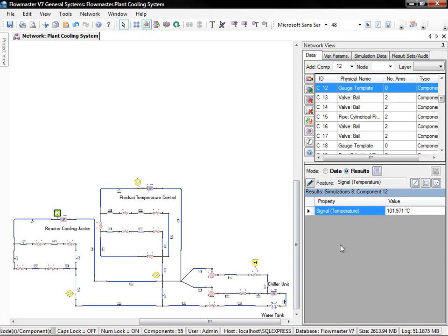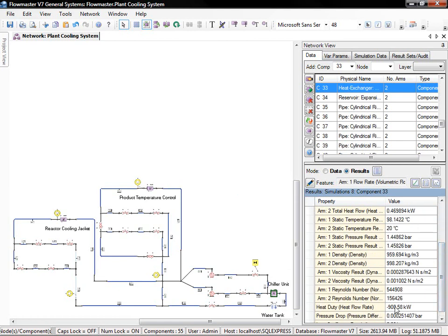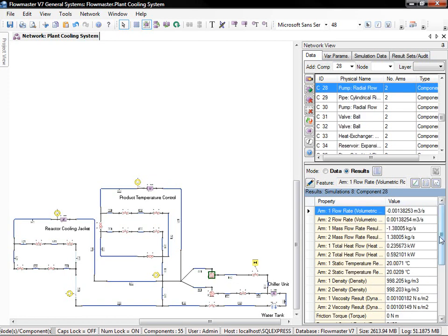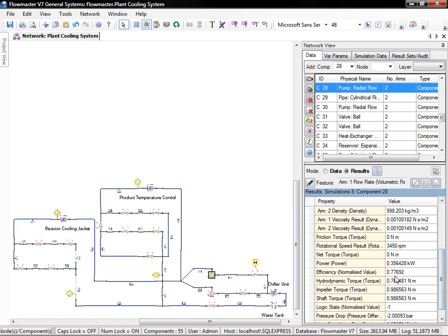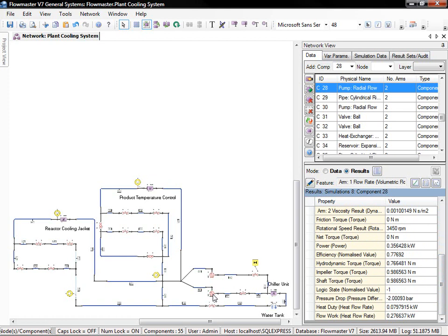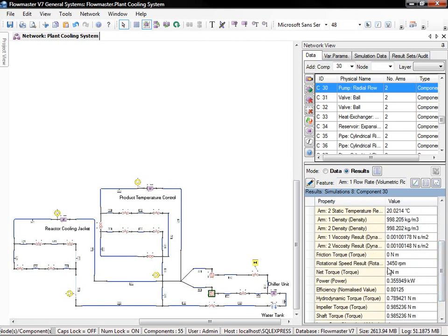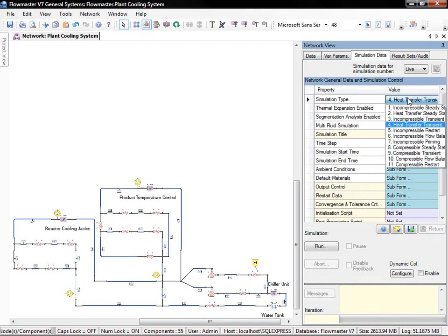also to investigate to make sure that the efficiency of the pumps is running in an adequate range, so that we have a little bit of energy that we can still put into the system should we need to move more water due to different operating conditions. So with this we can see that we have our system running at an adequate efficiency out of the pumps, and our cooling water is at the proper temperatures coming out of the different services.